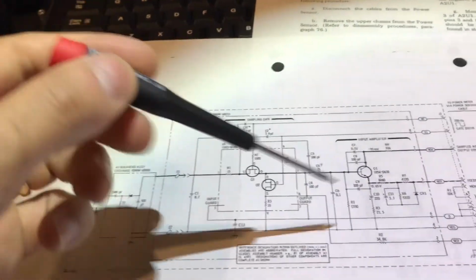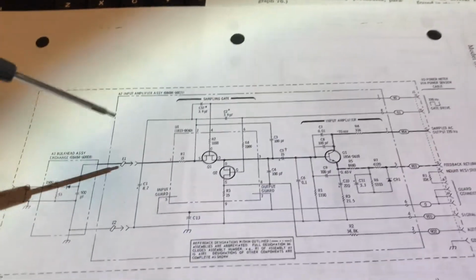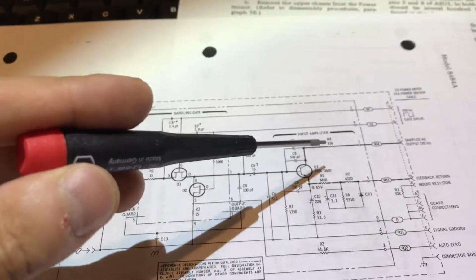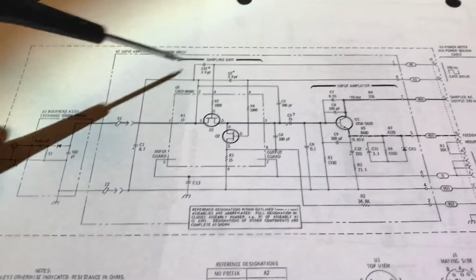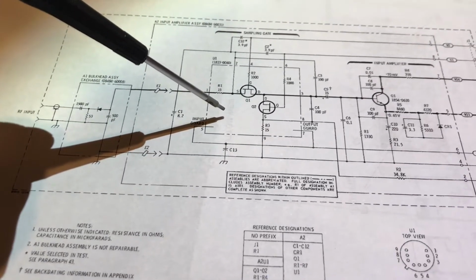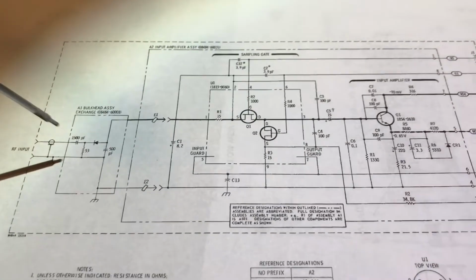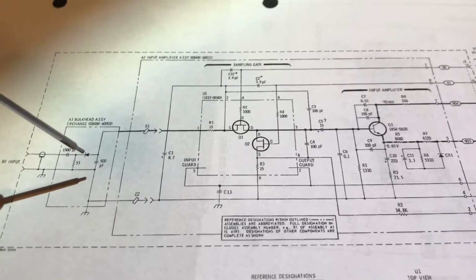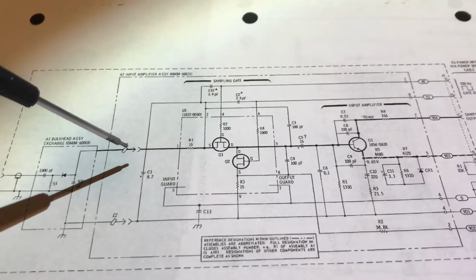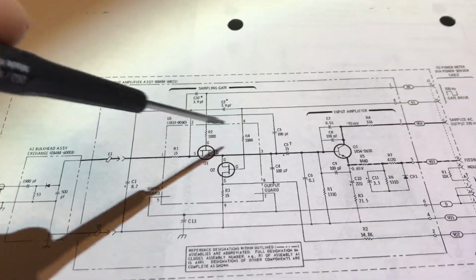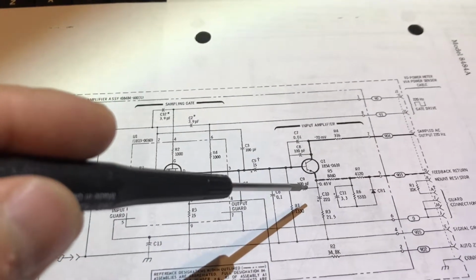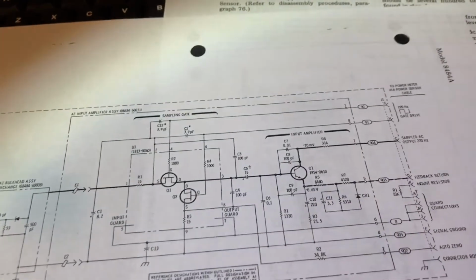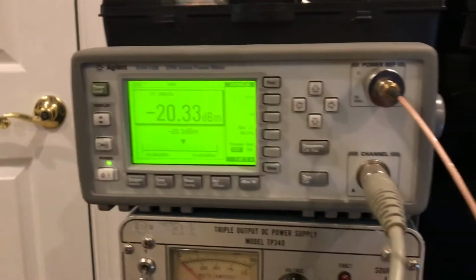If there was a problem in the amplifier circuit further on down, looking at the schematic, if there was a problem in the amplifier circuit down here, the input amplifier, then we wouldn't be getting a signal out at all to the power meter. Obviously the sampling gate and the input amplifier assembly is working correctly, because we know that the bulkhead assembly is working, because we got the approximately minus 5 millivolt signal at a full power input signal. And we know that the input amplifier is working correctly because it's producing an output to the power meter, which corresponds to the correct power level.